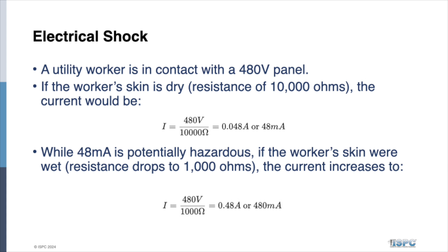And then if you lower your resistance, with that same 480 volt contact, so now we're down to that 1,000 ohm threshold we've been talking about, that current jumps up to 480 milliamps. We just said the fatality threshold is 100 to 200 milliamps. Well now you're double that, just because your resistance went from 10,000 to 1,000. So that's how narrow of a window we're playing in between just getting shocked or potentially being killed. And we need to understand those conditions that, if they change, can potentially be fatal.